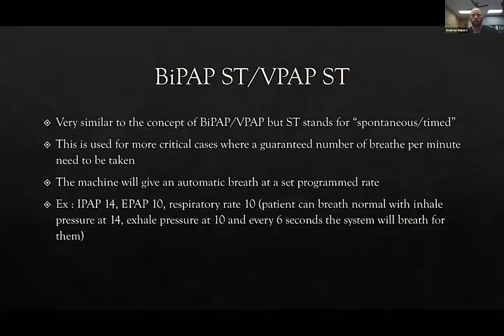Now, what I've found is this type of treatment does take a little bit more time to get synced with, depending on how aggressive that rate is. A normal respiratory rate can be between 8 and 14, or 8 and 16, depending on the person. So you don't want to set a machine to where it's going to out-breathe a patient. If you had a person on a rate of 20, it's like they're exercising, and the system is just constantly puffing at them, breathing at them, breathing at them. Every 3 seconds, they're getting a punch.